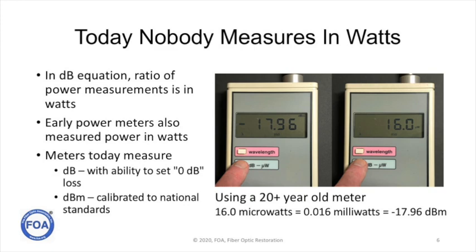Today in fiber optics, nobody measures in watts. They all measure in dB. Either dBm, calibrated to national standards, or dB to measure loss or gain. We had to go find a 25-year-old meter in order to show you what a measurement looks like of the same power in dB and in watts. And you can see we're measuring 16 microwatts, that's 0.016 milliwatts, which comes out to minus 17.96 dBm.